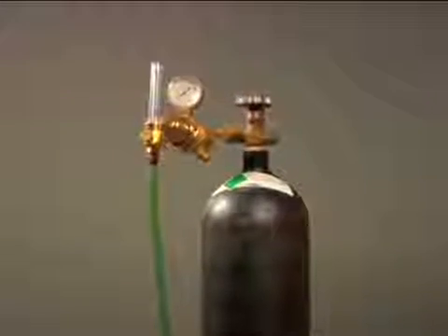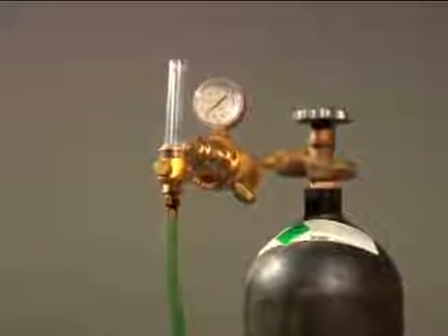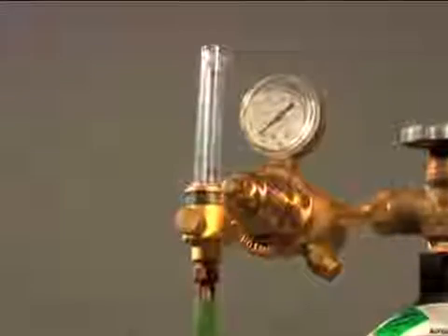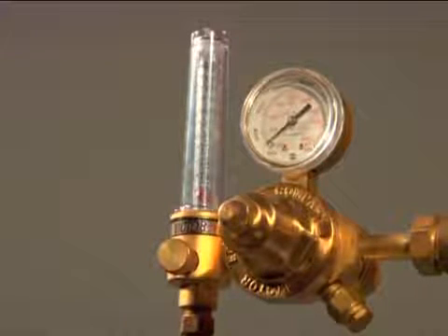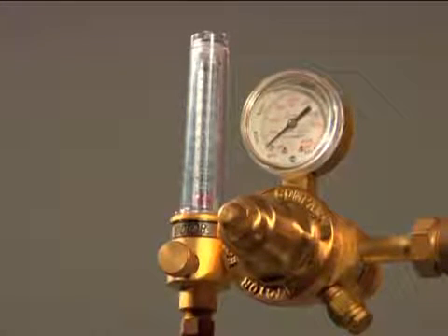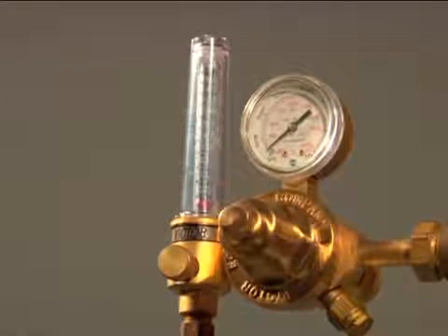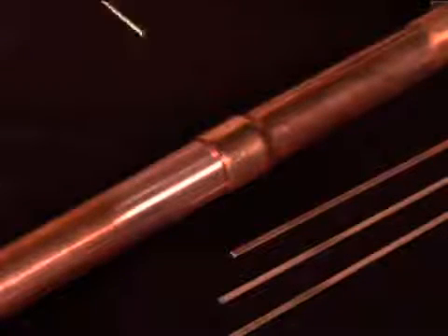Once the tube and fittings are assembled and ready for brazing, the piping must be continuously purged with an approved purge gas like nitrogen to prevent the development of copper oxides on the interior of the tube and the fitting. Be sure to keep the purge gas on until the completed brazed joints are cooled to the touch to prevent internal oxidation. Now we're ready to apply heat and alloy.